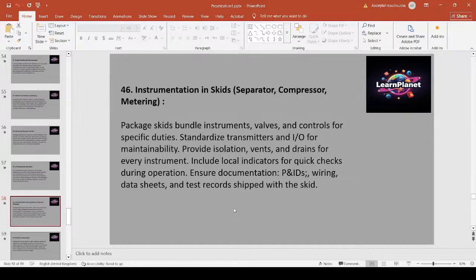Instrumentation in skids. Separators, compressors, metering. Package skids bundle instruments, valves, and controls for specific duties. Standardized transmitters and IOs for maintainability. Provide isolation, vents, and drains for every instrument. Include local indicators for quick checks during operation. Ensure documentation, P&IDs, wiring, datasheets, and test records are shipped with the skid.